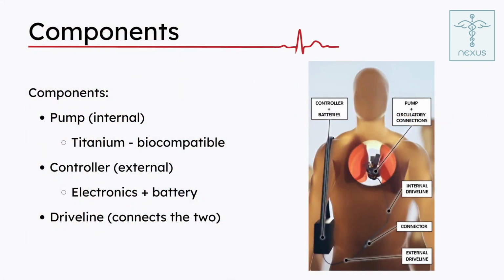So, the BiVACOR total artificial heart is made up of 3 components: the pump, the controller, and the driveline. The pump is the actual heart part that goes into the chest. The controller sits on the outside and has all the electronics and some rechargeable batteries. And it also has a driveline, which is essentially just the wires that connect the two. So there's a wire coming from the outside, one from the inside, and they have a little connector in the middle.